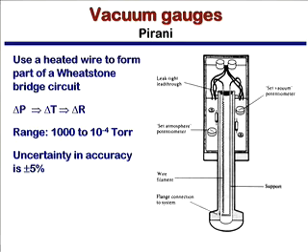In the case of the TEM, we're always trying to work well below 10 to the minus 4, so the only time you ever really interact with these things is when you've had a problem, right? You are up at air and you're trying to pump your system down. You use the Pirani gauge to go, okay, looks like it's going the right direction. Yep, going down, going down, going down into the 10 to the minus 4. And then at that point, other pumping systems will kick on to pump down to lower and lower levels of vacuum. Okay, so it's really just a gauge to see, am I going the right way?